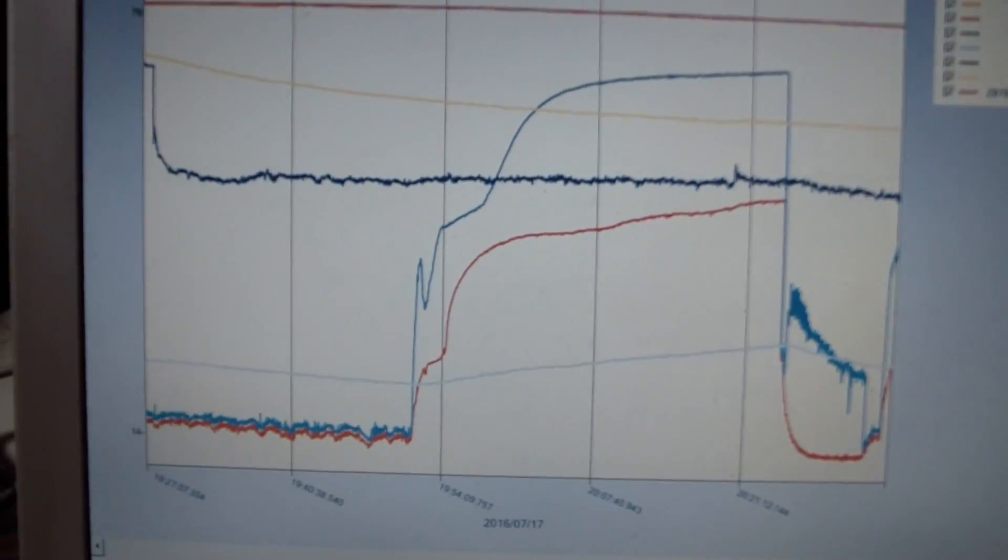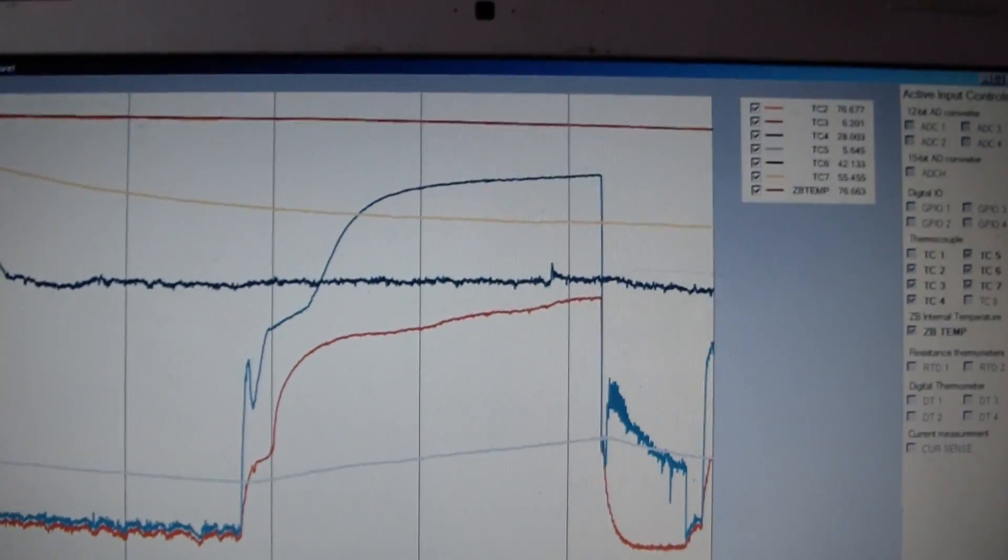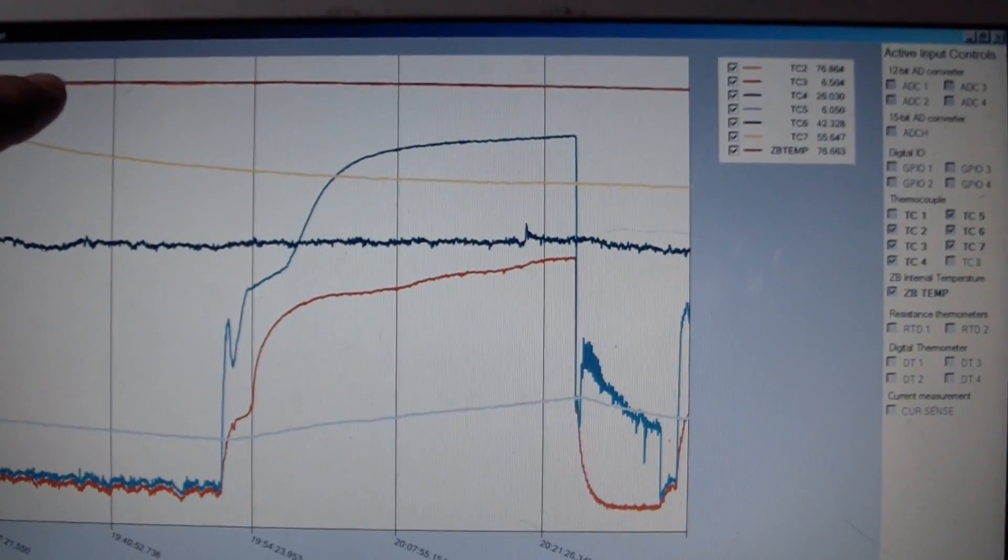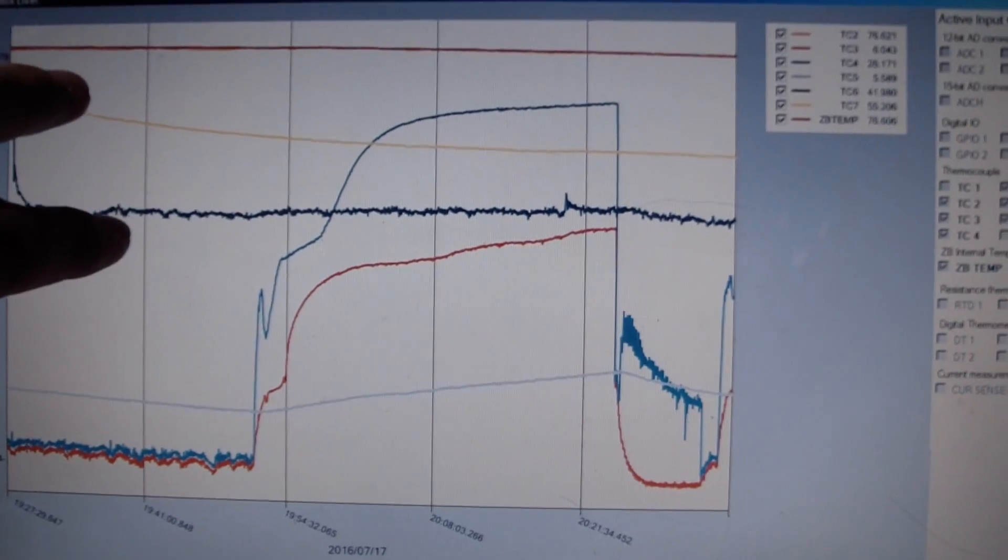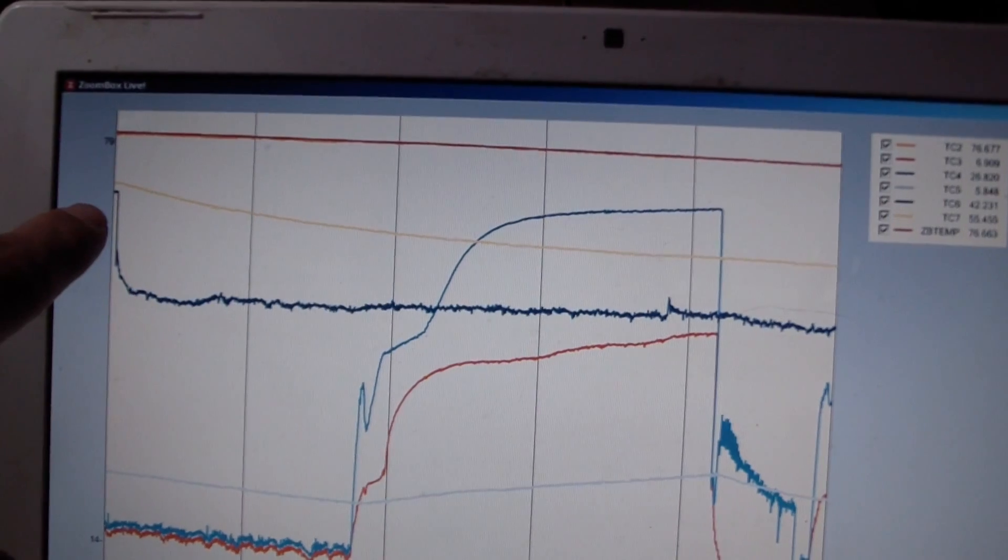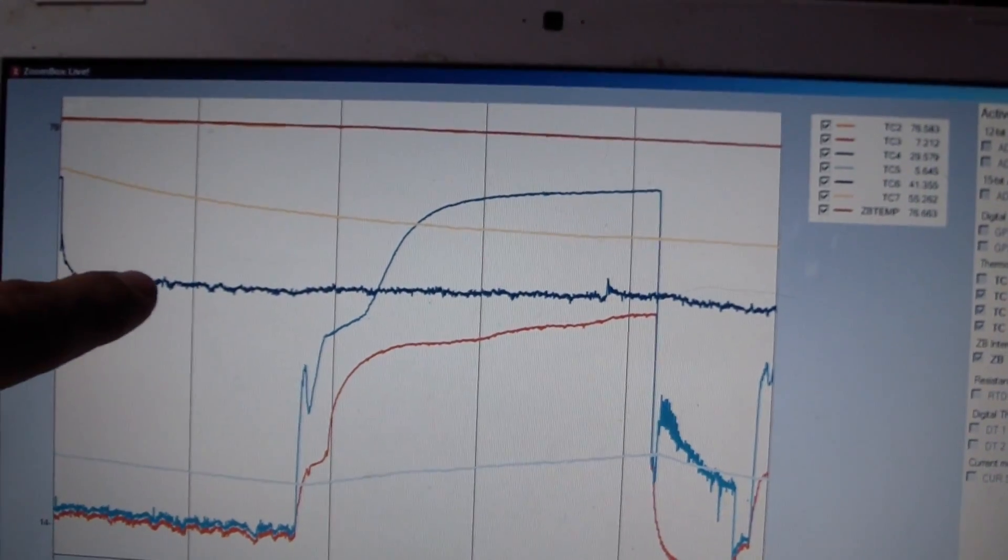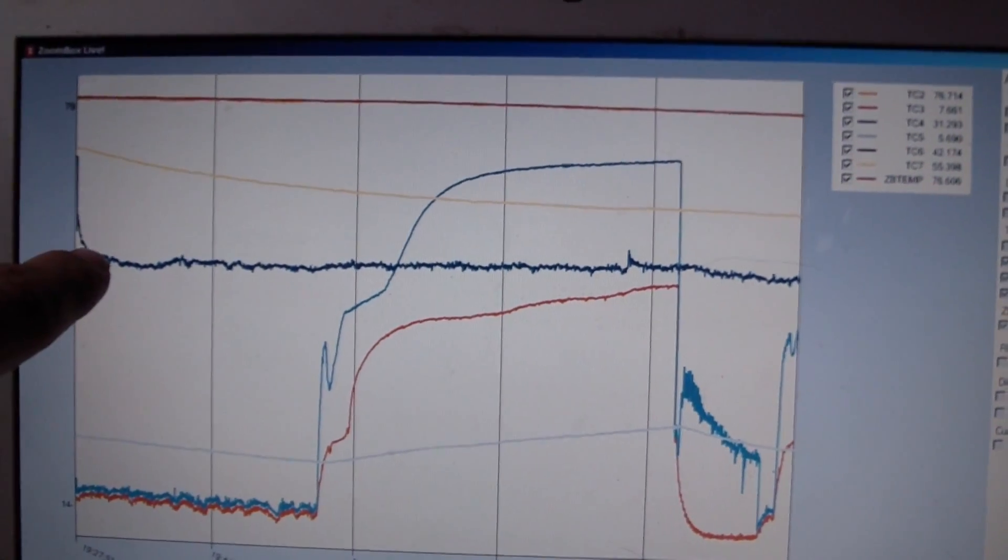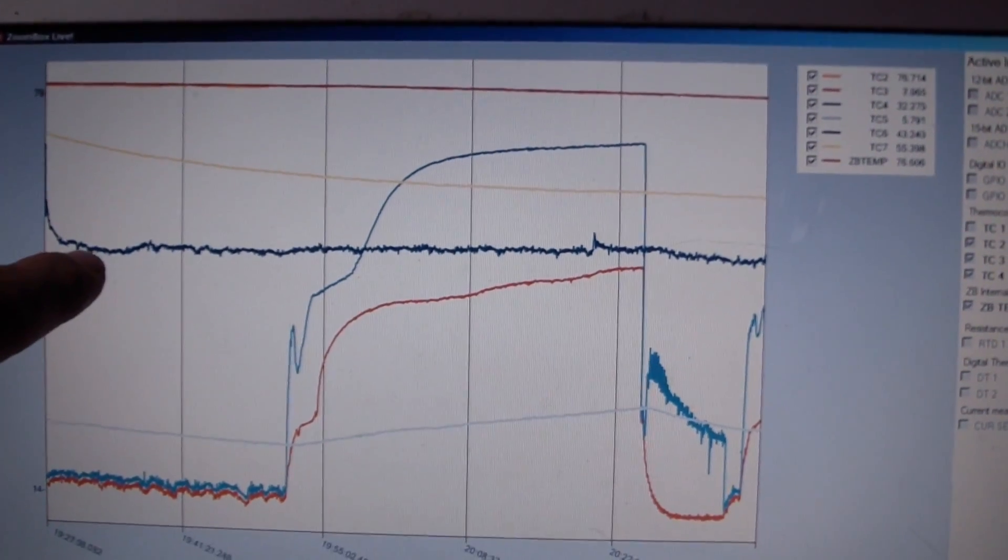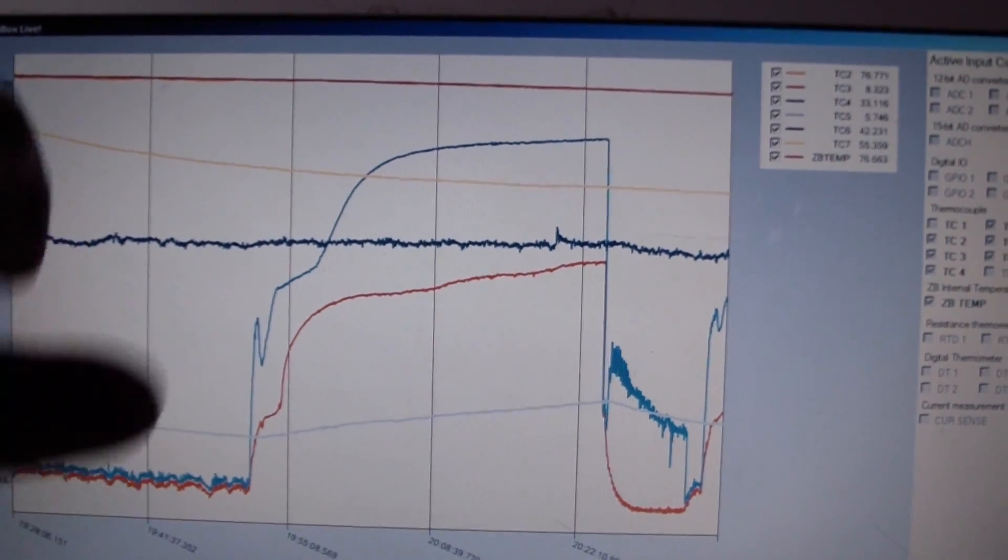First I want to share a little bit of the observations with the data here. I will eventually collect some data and display this a little bit better. What we have here, the very top line is pretty much ambient temperature. It's also the subcooling, so that's a lot of subcooling that I'm getting. The yellow line here below, there's actually two air temperature sensors in there now. Before there was only one. I'd like to point out this blue one that's just about off the screen now. You see where it dropped suddenly? That's where I reinstalled that temperature sensor at the bottom of the baffle. Warm air rises to the top of the cabinet, goes over the top of the baffle and then descends and is cooled. That's the reason that dropped there, because I repositioned it. The yellow one is at the top of the baffle and the blue one's at the bottom. There's usually about 13 to 16 degrees temperature difference between those two values, so I'm definitely doing some air cooling.